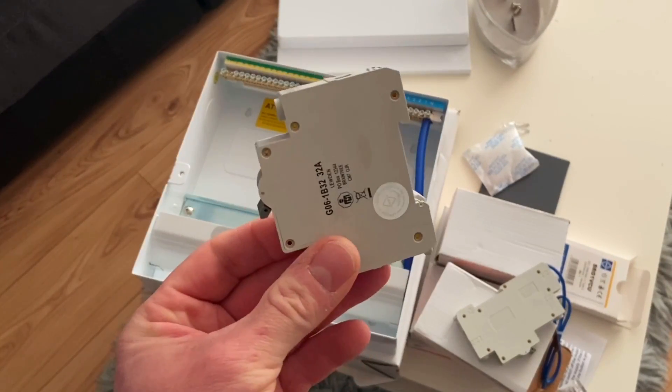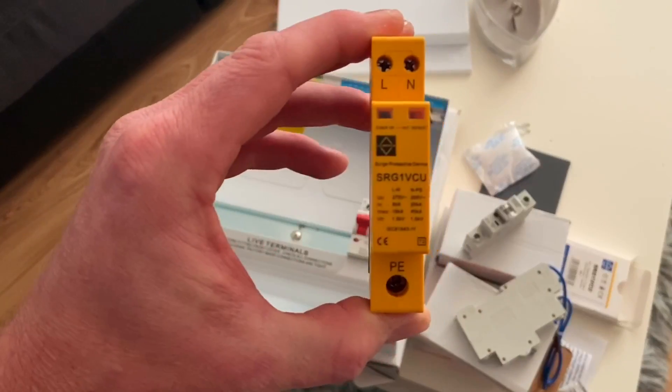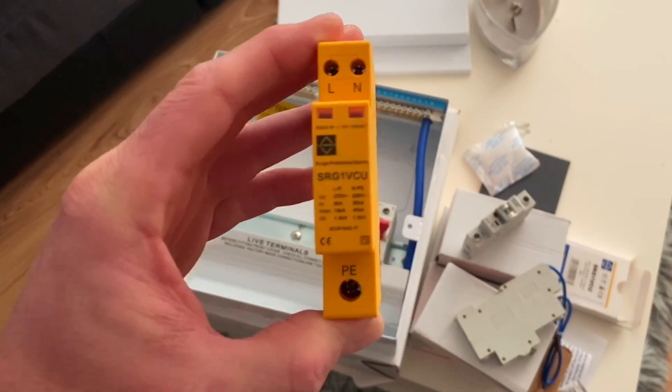One breaker - a 32-amp - is non-RCD protected. The reason is there's a small summer house at the end of the garden with an SWA cable running to it, and there is RCD protection in the summer house itself, so we're not putting it on RCD in the house. We can also see just there the lightning symbol - an SPD is going to be fitted.